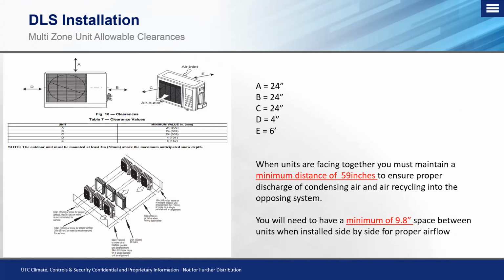So for clearances for our outdoor unit, you can see on the diagram on the left, and then the A through E selections up on the top right of the screen are going to be our minimum clearances that we require both on a single and a multi-zone configuration. So let's look at point A on here. Point A is going to be from the top side of the unit to the object that's going to be directly above it, if there is one. We need a minimum of 24 inches of clearance there because this top cover needs to be taken off to gain access into the electrical section.